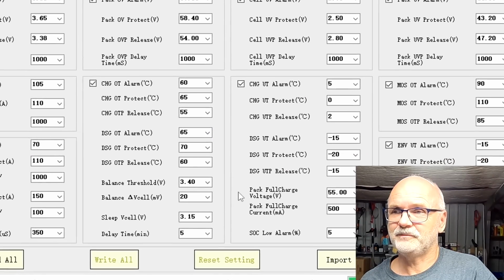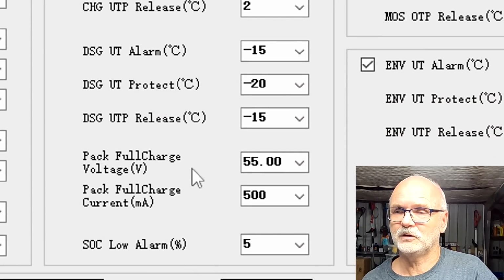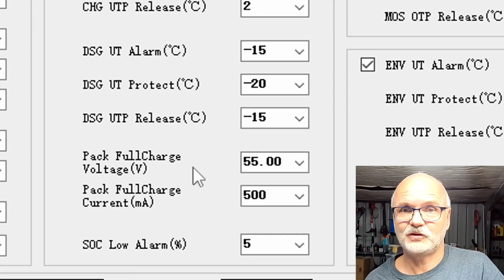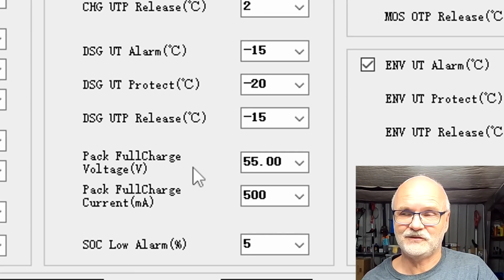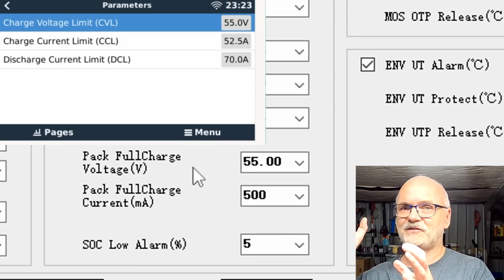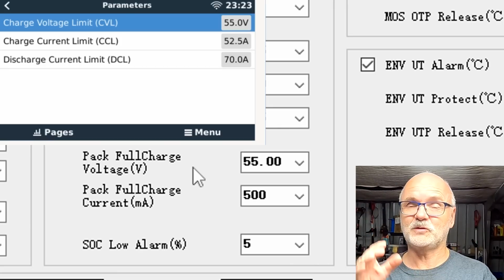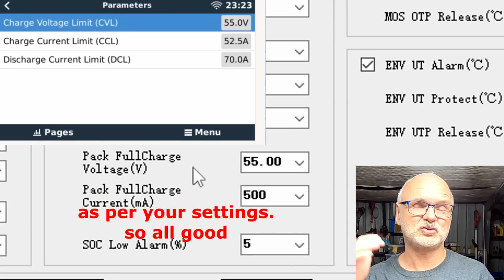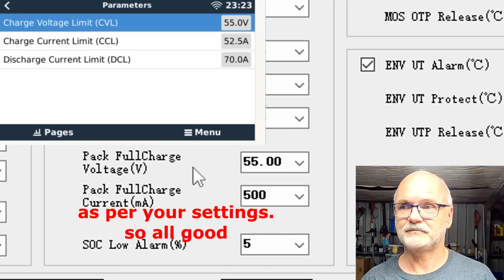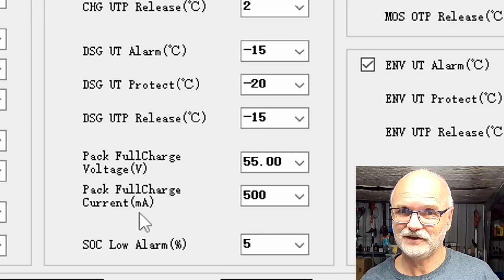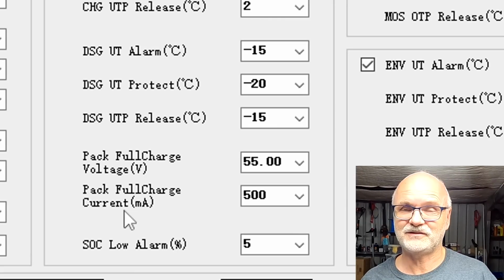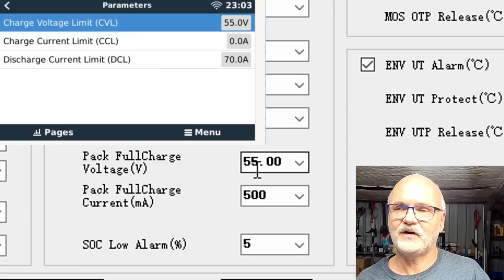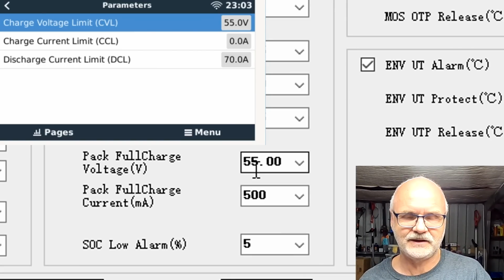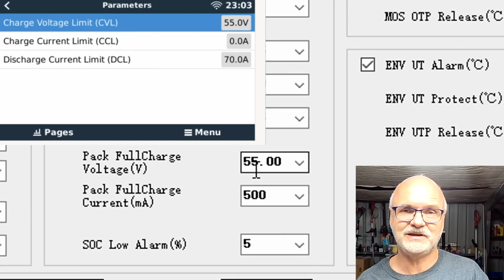Going back to the parameters, the Pack Full Charge Voltage is 55 volts. This is exactly what you can see here in the Victron system as well. And if you would let the BMS control your system, it would make the MPPT or your inverter charge to 55 volts only. I'm not sure what the full charge current is for then, if it doesn't reset to 100%. But as we have tested, it doesn't. And once you hit the 55 volts, you can see this here in the Victron system again, the charge current from the MPPT or your inverter would go to 0 amps.